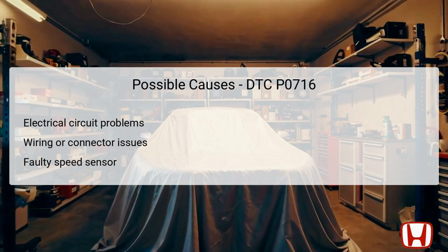Additionally, the speed sensor itself may be faulty or malfunctioning, producing inconsistent or erroneous data about the turbine speed. It is important to perform a thorough visual inspection of the wiring and connections, as well as a functional test of the sensor. Each of these potential causes must be examined diligently to isolate the issue effectively.